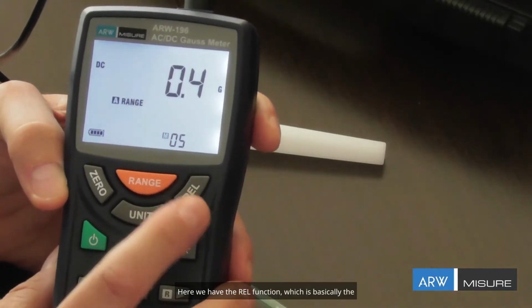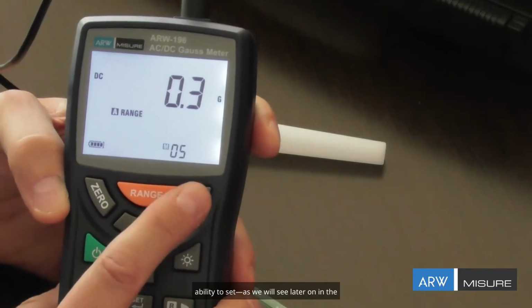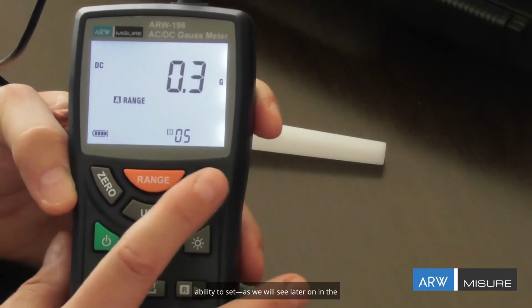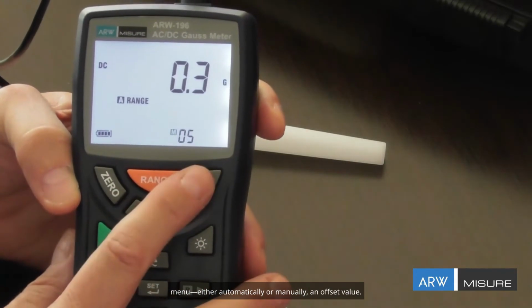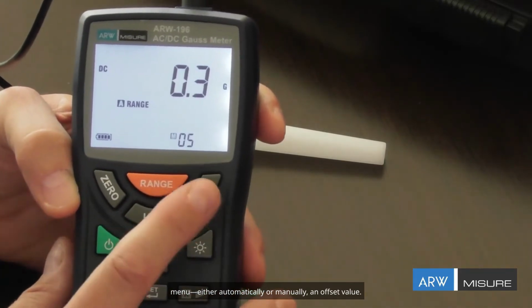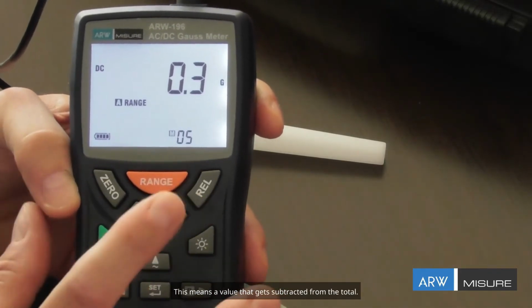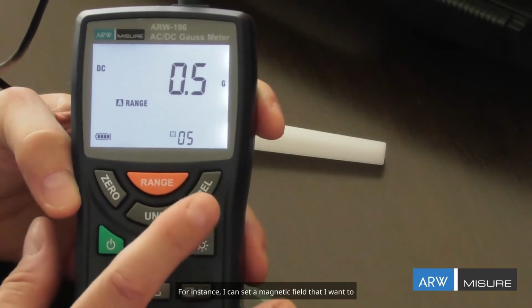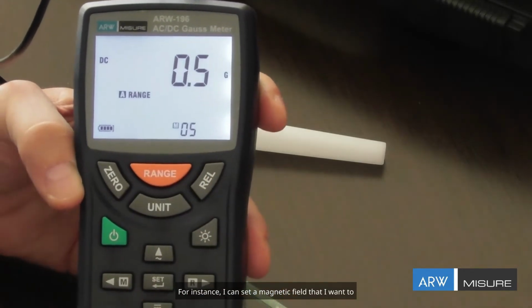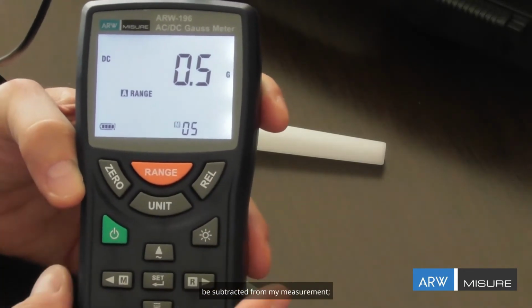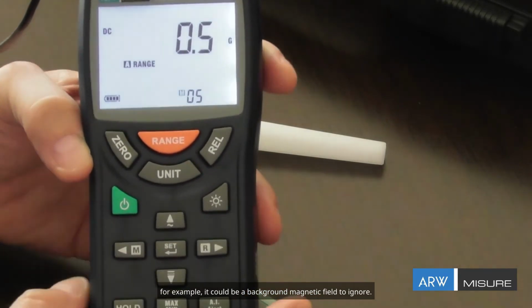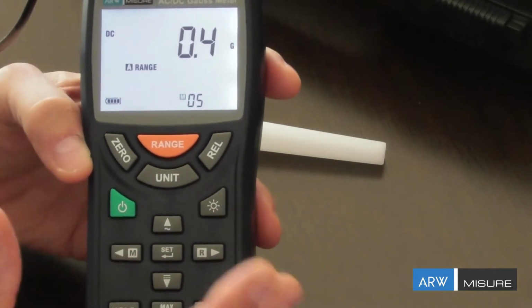Here we have the REL function, which is the ability to set, either automatically or manually, an offset value. This means a value that gets subtracted from the total. For instance, I can set a magnetic field that I want to be subtracted from my measurement, such as a background magnetic field to ignore.